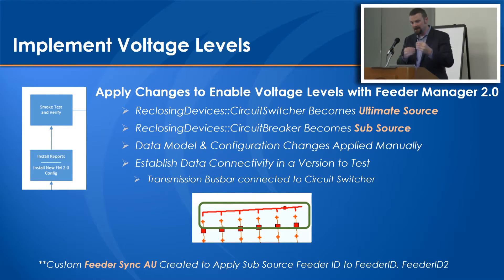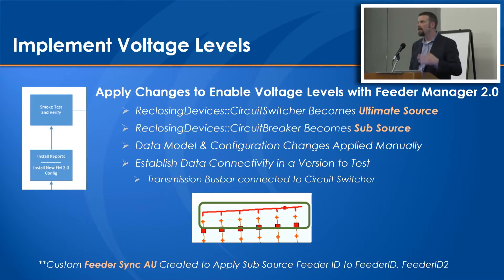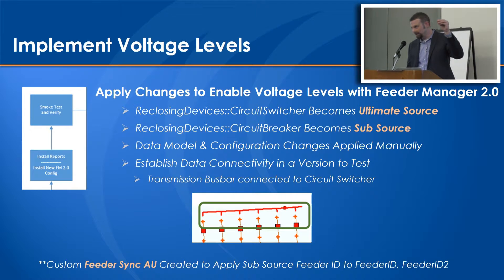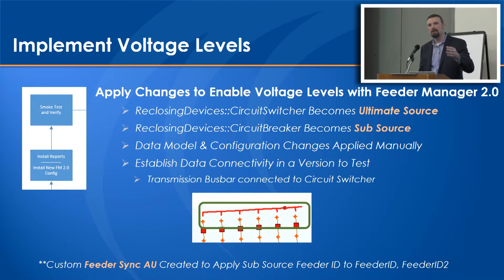It's a fundamental change in the way these networks are built to a new common source point. One challenge is they use the Feeder Sync process, which uses in-memory circuit numbers captured while you're editing. It decreases conflicts and increases performance. After posting a given version, it takes those IDs and puts them back into database fields - important because a number of extract and analysis processes utilize those fields to pull circuit IDs out. When we moved to using the ultimate source, there was now a new Feeder ID being written, which is a transmission-level circuit ID. That didn't work for the process, so it required some customization around the Feeder Sync process - a new plugin to say, for the extraction process, we want to continue to use our distribution circuit numbers while still maintaining connectivity up to the transmission network, getting the best of both worlds.